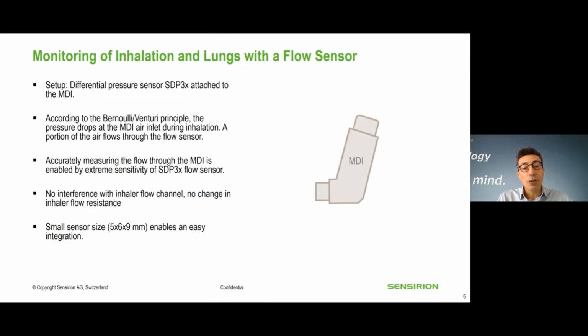Let us have a deeper look at the technical implementation to perform the previously mentioned measurements. We used one of our differential pressure sensors, the SDP3x, also used as a flow sensor. This is the latest generation of small footprint, low power, and high accuracy flow sensors. We attached the sensor to a metered-dose inhaler.